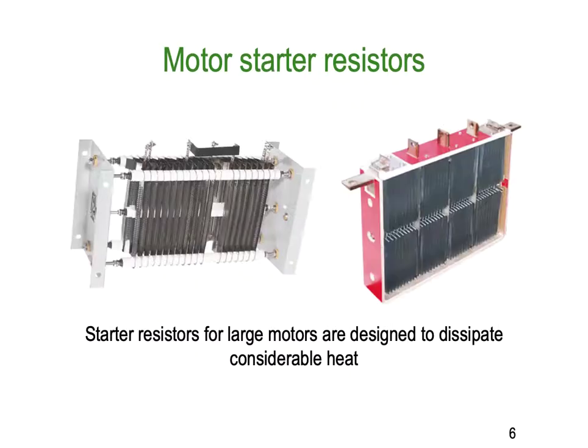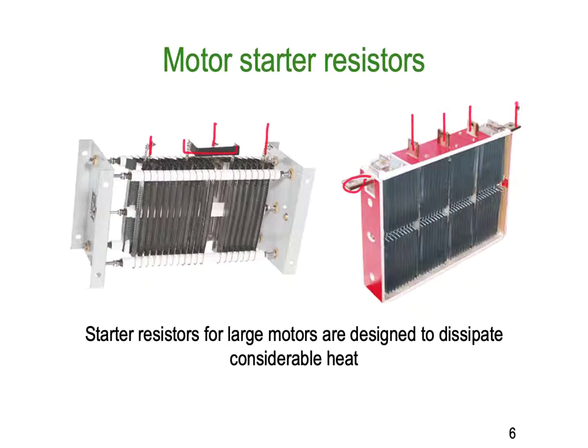That's a staged lever arm speed controller to bring up the speed of a DC motor, to bring it online and account for its high start currents, by putting some resistors in series. Here are some pictures of those motor resistors. You can see they're quite large — low resistance values but large wattages — because they have to dissipate a fair amount of energy that would have been absorbed by the armature. You can see they're connected in stages with connections at multiple tapping points. They often have to be mounted somewhere well-ventilated so the heat they produce at start can be dissipated quickly and easily.